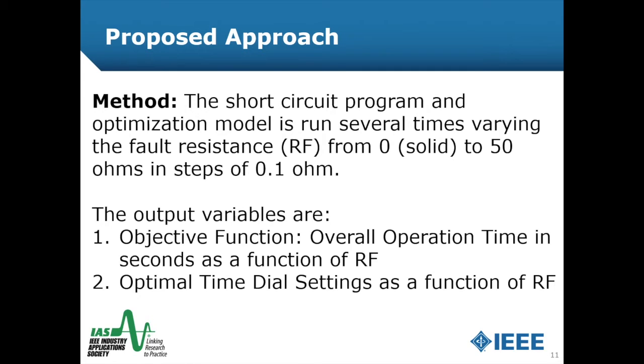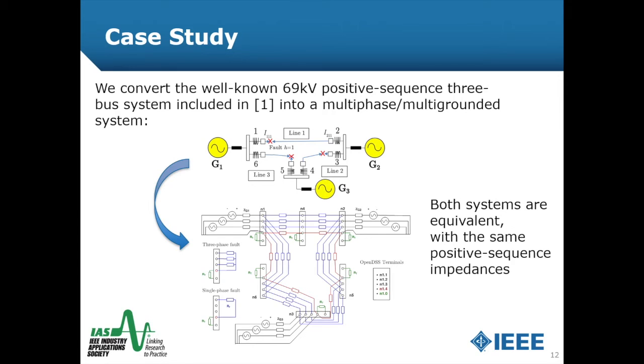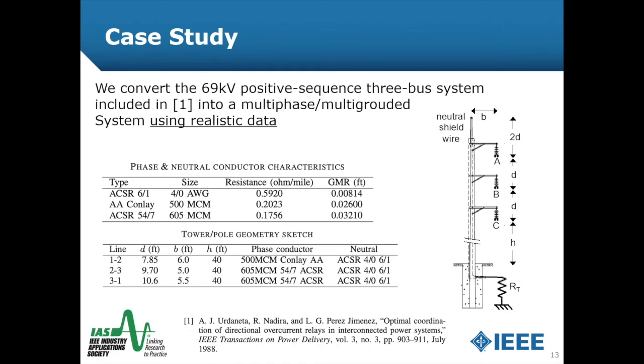The process to validate the optimization approach involves running the optimization model several times, varying fault resistance from 0 to 50 ohms in steps of 0.1 ohm. The output variables are the objective function to assess speed and the optimal time dial settings (TDS) to observe variation due to fault resistance. We used the well-known 69 kV positive-sequence 3-bus system from reference 1 and converted it into a multi-phase multi-grounded system using OpenDSS, with both systems being equivalent in terms of positive-sequence impedances.